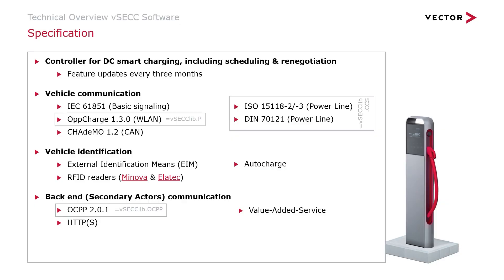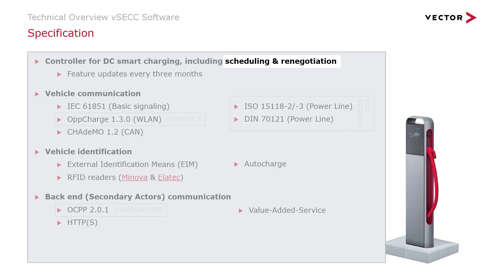Here you can see the current specification. First, I want to show you the new product features. When the available power for charging changes over time, charging schedules are advertised to the connected EV. The schedules contain how much power is available at a certain time. These schedules can either be set to statically contain the maximum power of the power electronics, or they can be computed from charging profiles that are provided by a charging station management system via the OCPP interface.